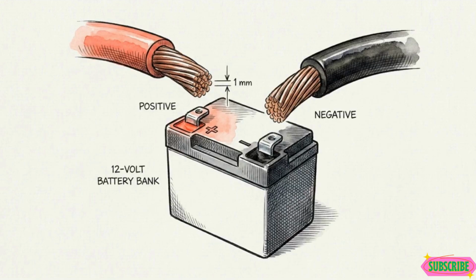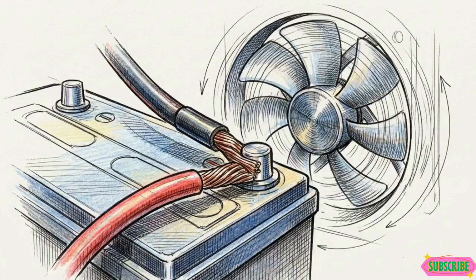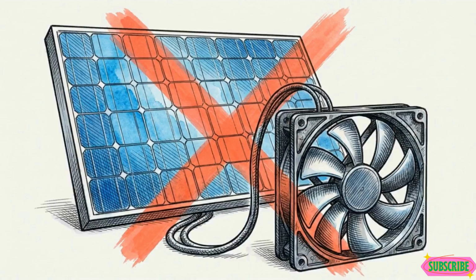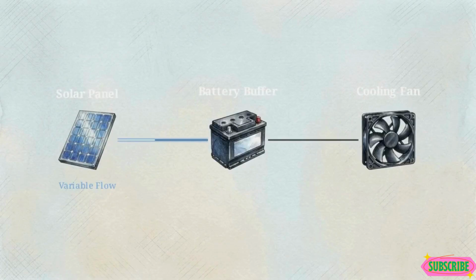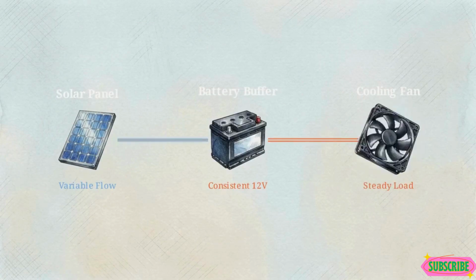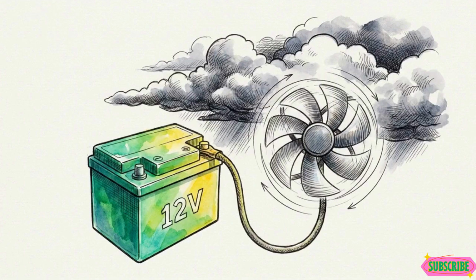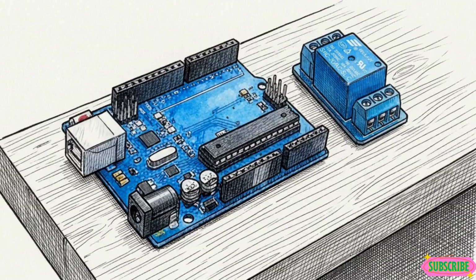Before wiring any smart controls, we must verify the fan works with our power source. Test the fan directly against the 12-volt solar battery bank. Do not wire the fan directly to the raw solar panel itself, because the panel's output drops drastically the moment a cloud passes by — relying on a battery buffer solves that fluctuation problem. A fully charged 12-volt battery ensures the fan spins at maximum speed whenever the system calls for cooling, regardless of the immediate shade outside. Now we set up the electronic controls.